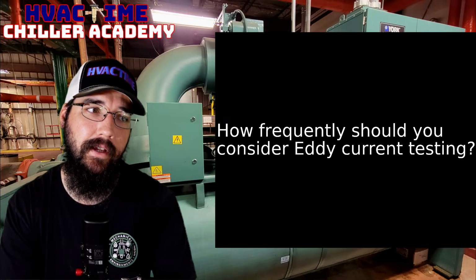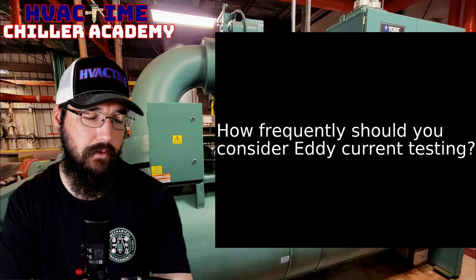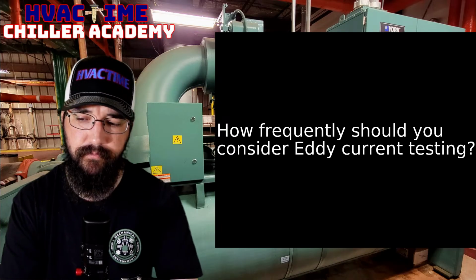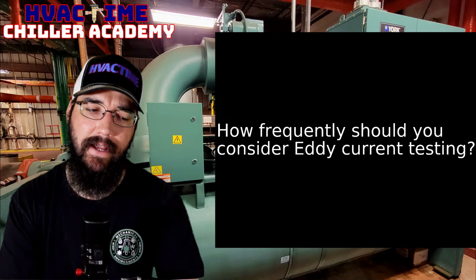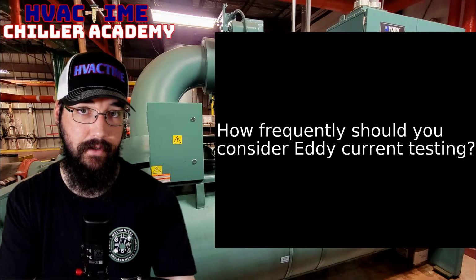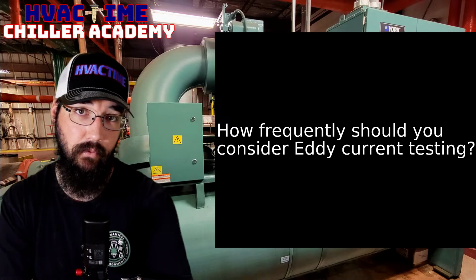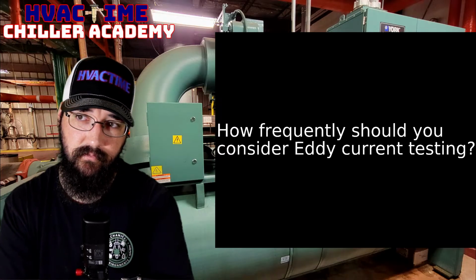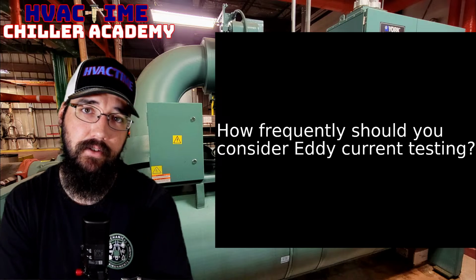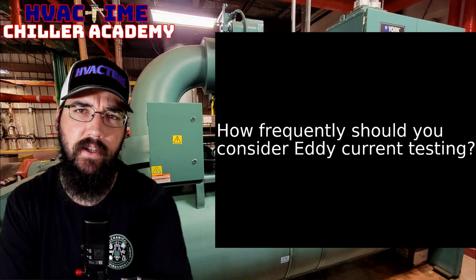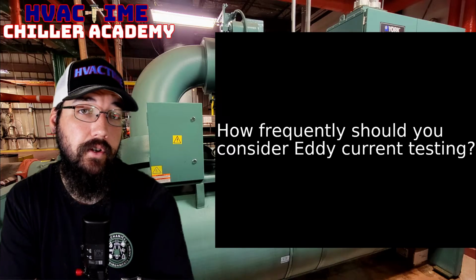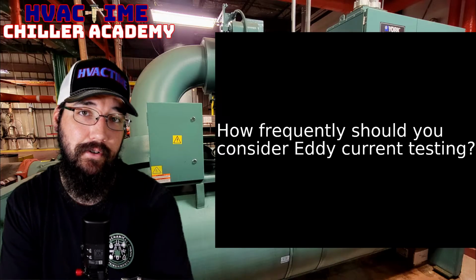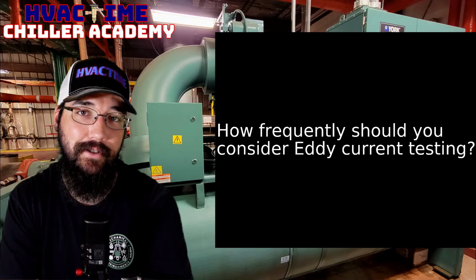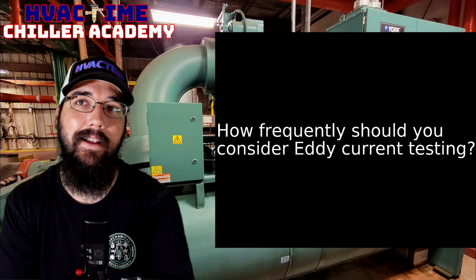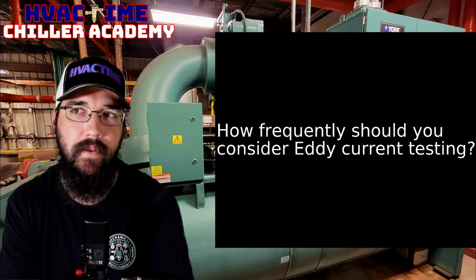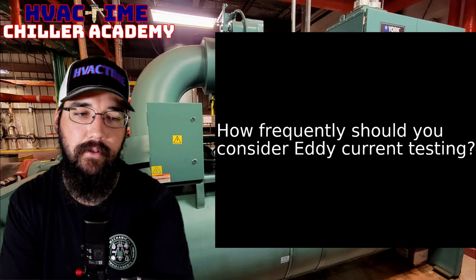Really important that we try to catch that sooner than later. That particular plant was very resistant because it was a complicated situation, but we were having major leak issues, because those condensers were heavily damaged by the strainer problem. Not to mention they also had flow issues, since strainers had gotten sent through their pumps, and the pumps were struggling to survive. So it became this whole self-feeding cycle of failure.